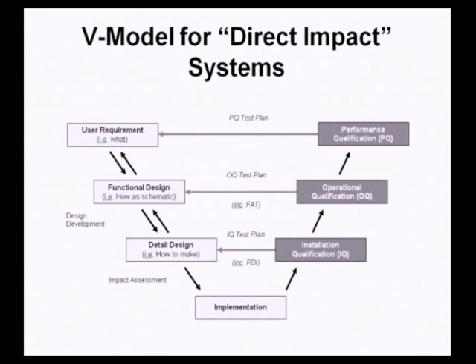Looking at our development inputs and outputs, we've seen the V-Model before for direct impact systems. Our URS is related to our performance qualification protocol, our functional design documentation is related to our operational qualification protocol, and our detail design documentation is related to our installation qualification protocols.